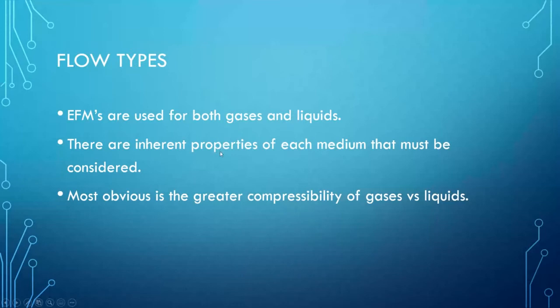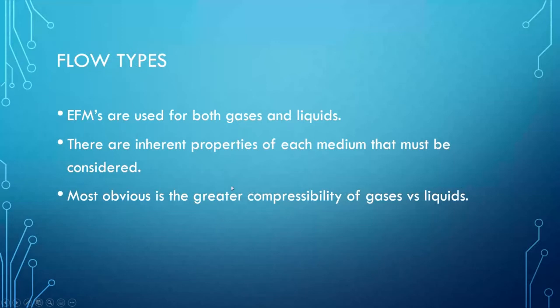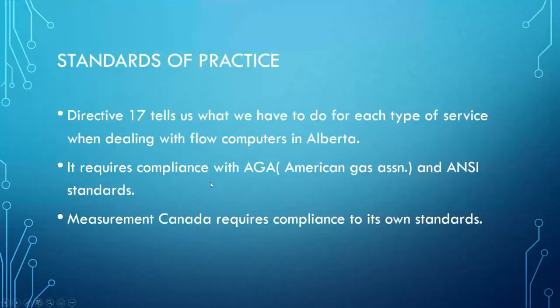When dealing with gas and liquid applications, we have to be aware of the properties of each medium to know what needs to be configured into a flow computer. The most obvious variable that differentiates gas and liquid flow is the compressibility of gases versus liquids. Compressibility comes into play when doing conversions between flowing conditions and standard conditions, and it's probably the biggest differentiator between the two fluid mediums.